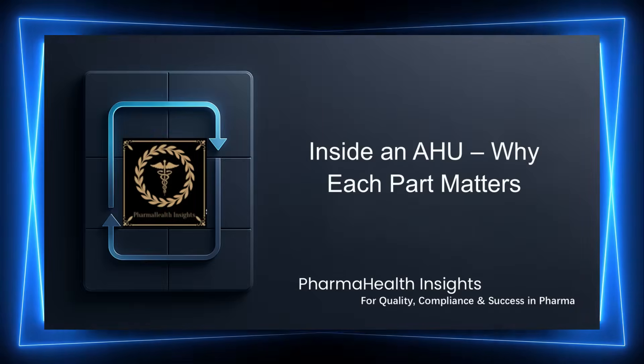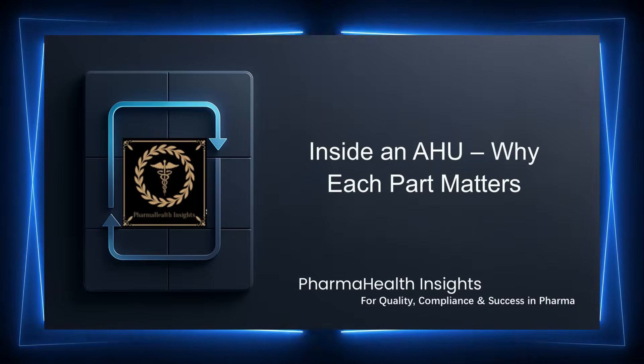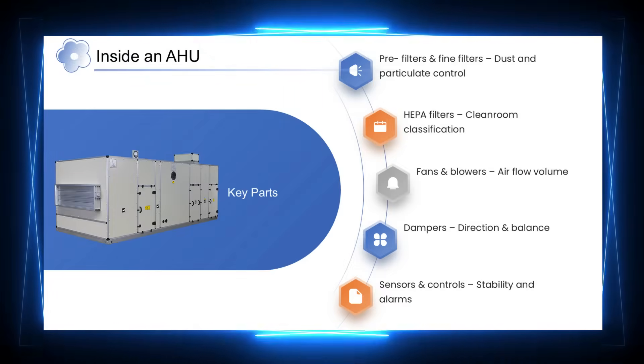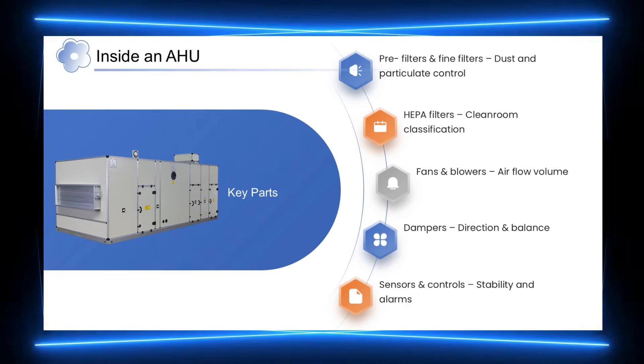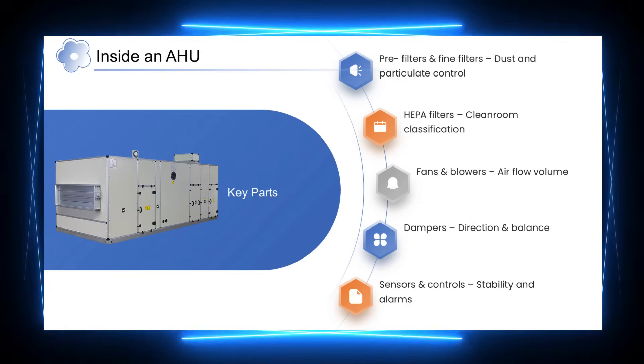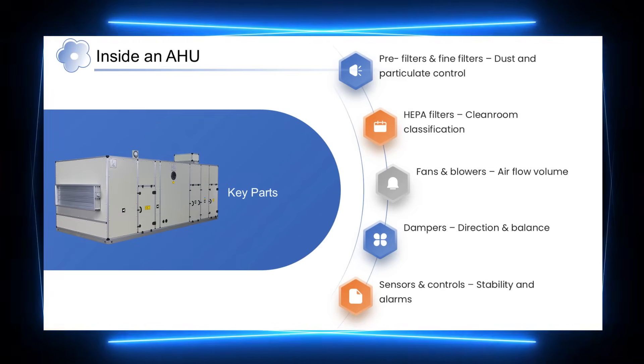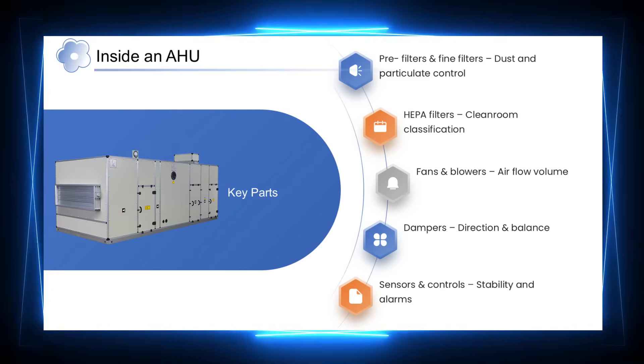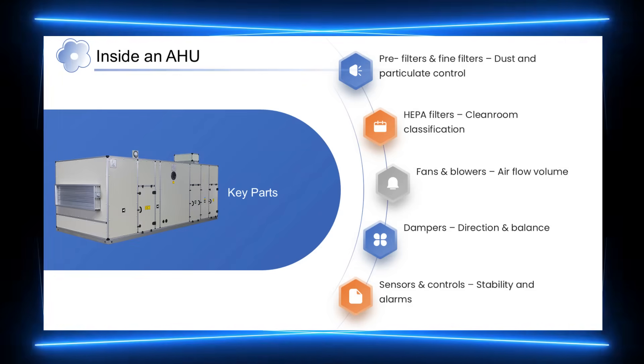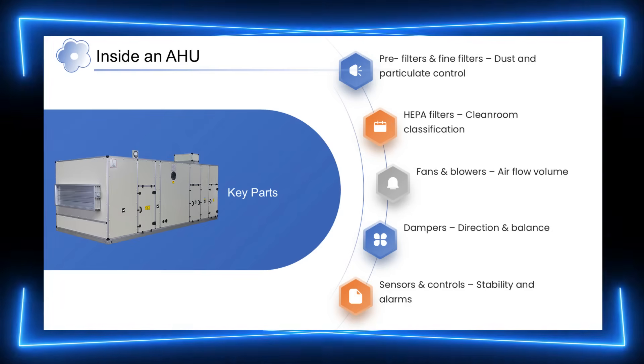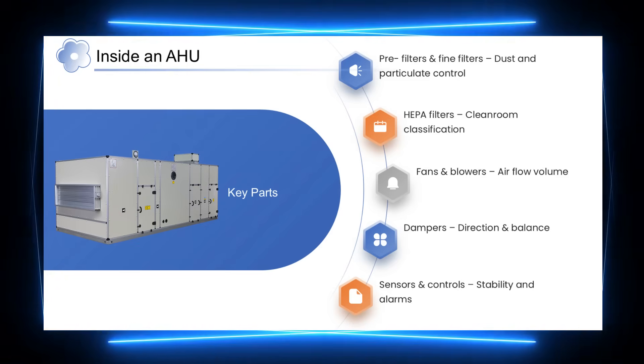To understand this importance, let's look inside an AHU. Inside an AHU, each component has a specific role in maintaining GMP control. Pre-filters and fine filters remove larger particulates and protect downstream components, while HEPA filters ensure the required clean room classification is achieved. Fans and blowers maintain the necessary airflow volume, and dampers help control airflow direction and pressure balance between areas. Sensors and control instruments continuously monitor system performance and provide alarms when conditions move out of limits. Together, these components ensure that air quality remains controlled, consistent, and compliant.